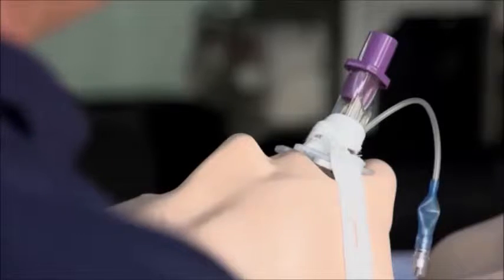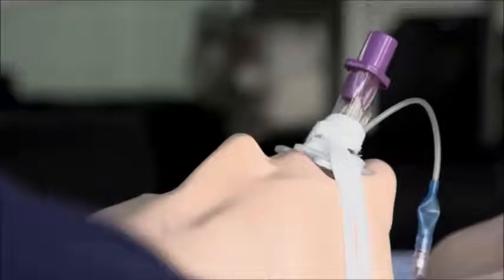Confirm that the patient's airway is protected. Keep the patient's mouth open to vent vapor. Keep the patient's head horizontal unless otherwise indicated by patient treatment requirements. As is standard of care, keep an eye on the patient's oxygen saturation levels throughout the cooling process. Note, it is important that you do not position the coolant bottle above the level of the patient's head, as liquid may siphon down the cannula to the patient.